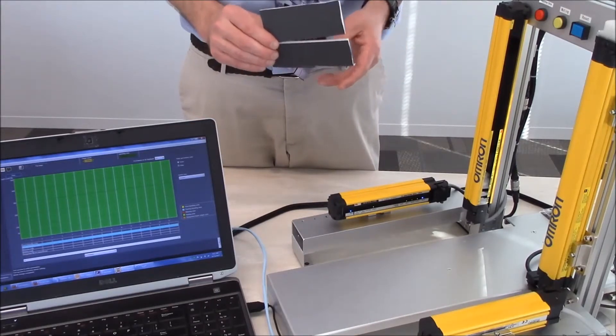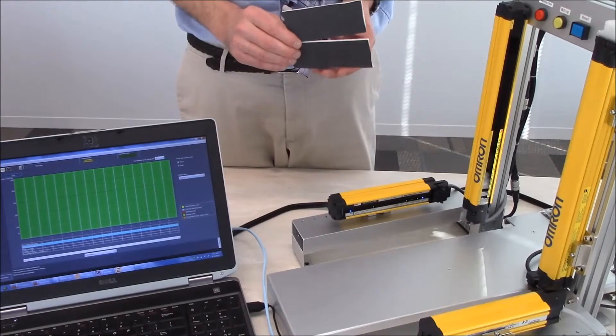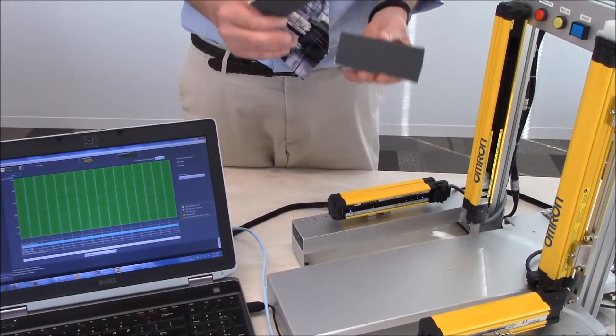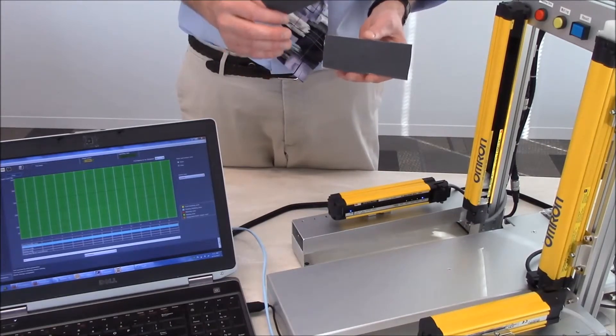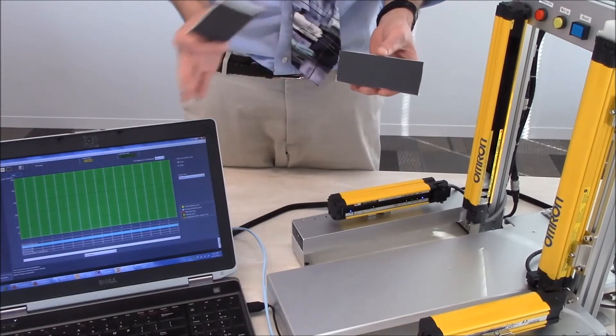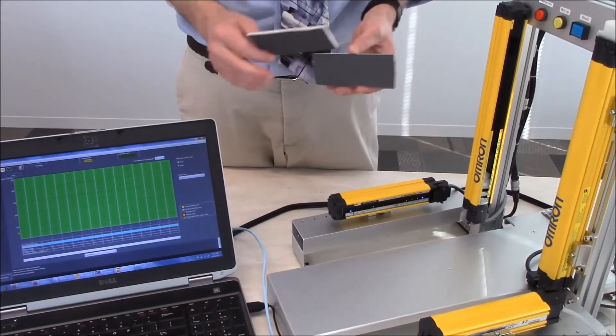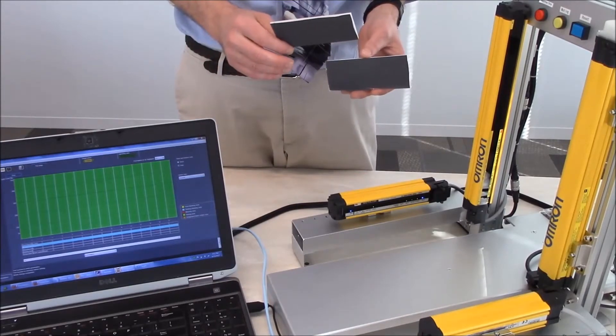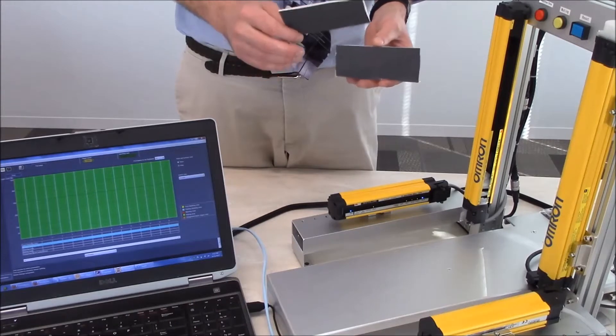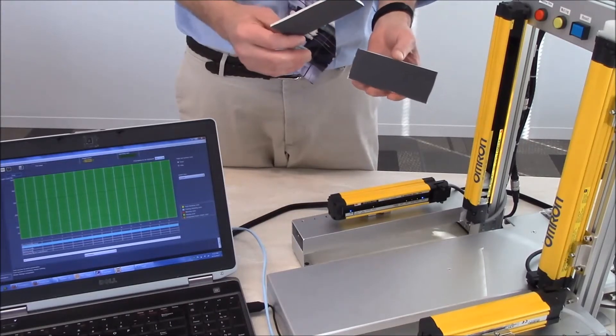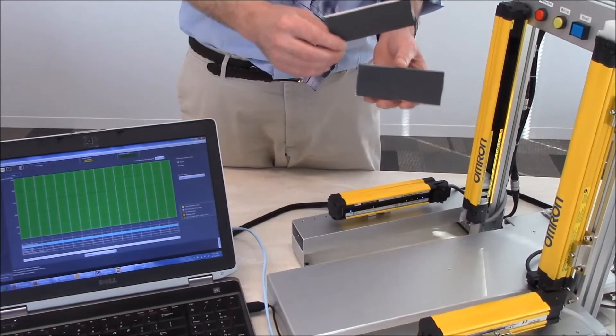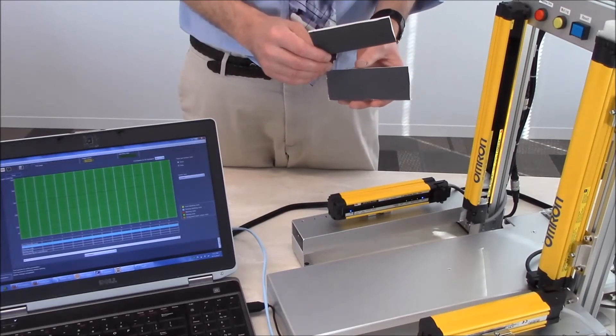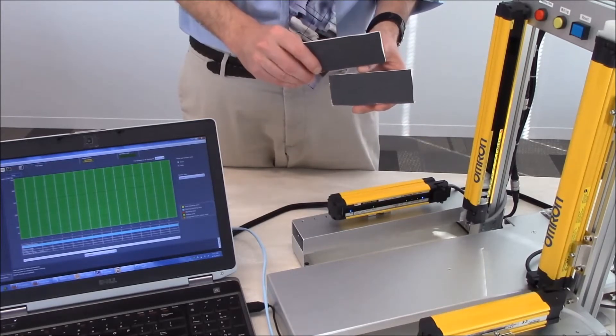Now with the reduced resolution, that allows you to do multiple items as long as you don't exceed the number 3, in this case the way that we had set it up in this presentation. As long as you don't exceed 3 beams, you should be able to put objects into the light curtain area without tripping the light curtain.